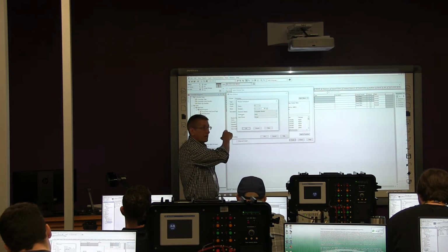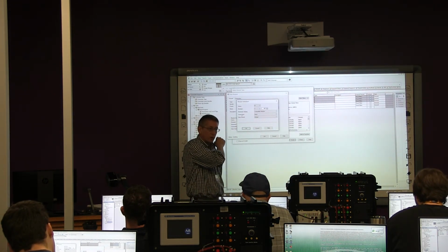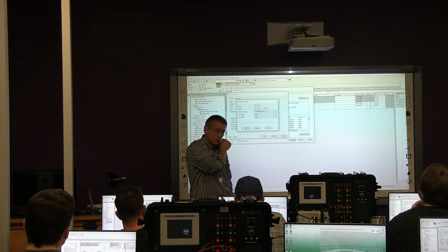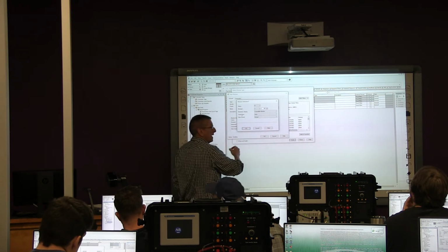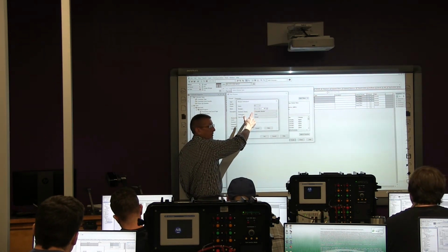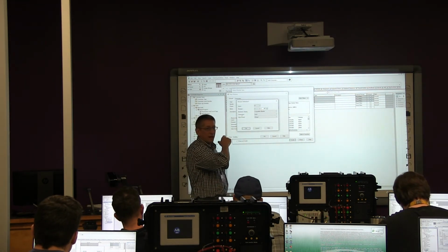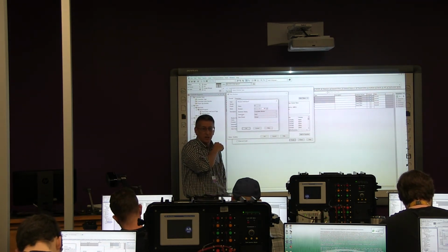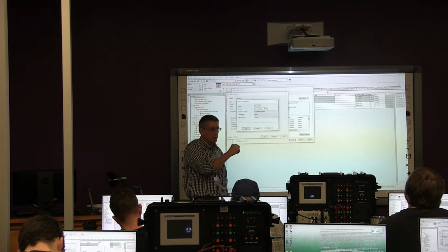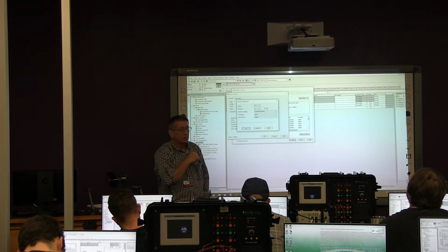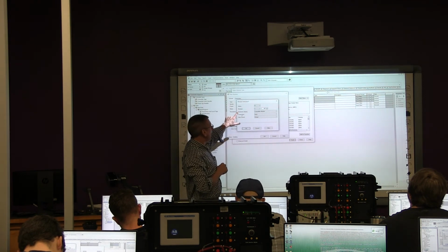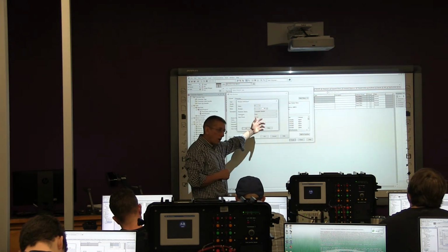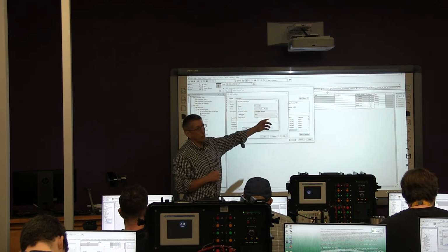So, all the modules, they have these revisions, right? And this is key information that you'll need to know and want to write down for next Thursday. They have a major revision on the left and a minor revision. And that refers to the firmware of the module. So it's like the ROM or the EEPROM that's inside the module. That's the firmware. This particular module, the major firmware just happens to be a value of 1, the minor has to be a 001.